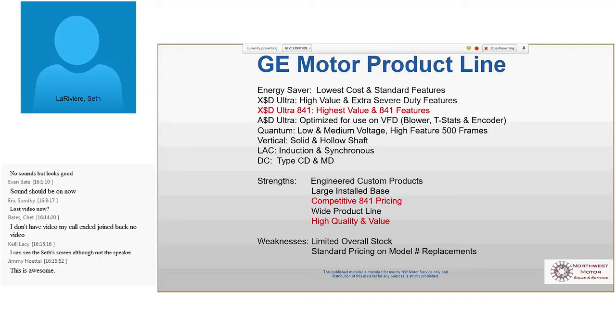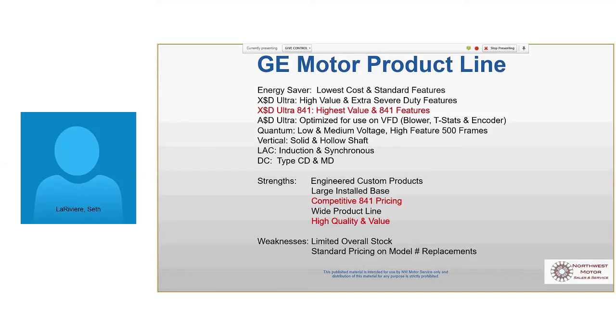They'll have a blower on them because in everything with the motor, well, all things electrical really, heat is the enemy. So anytime we're able to have a motor run cooler than it's designed to run, we really extend the life of the motor windings and the bearings, the grease in the bearings, and they just last a lot longer. The problem is on a true VFD rated motor, where we say it's optimized, that's when guys are going to run really, really slow.